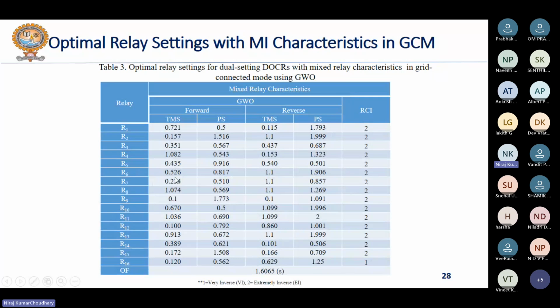So you can see that in this case, when the objective function value is calculated with mixed inverse type of relay characteristics, then it comes to 1.6065 seconds. Means this is the total time of operation of the relays after considering all the possible fault locations and operation of the associated relays.